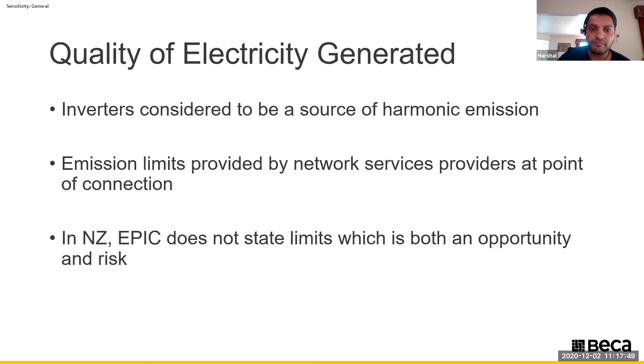This can lead to additional costs which may not have otherwise been factored in. So a lot of people are looking at allowing for harmonic filter banks as part of their project. Whether they need it or not is a different issue. But a lesson learned, particularly with one of the projects we're developing in New Zealand, is allowing for it in the event that over time voltage distortion becomes an issue, there's a provision for installing a filter bank to offset or rectify the issue.